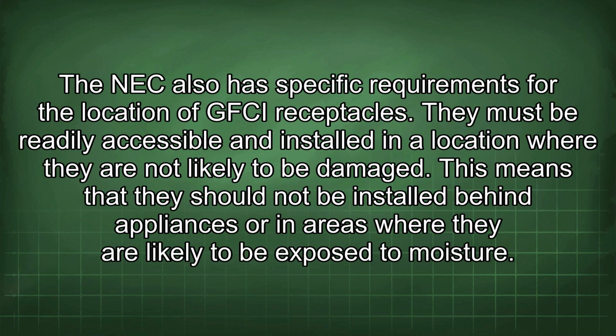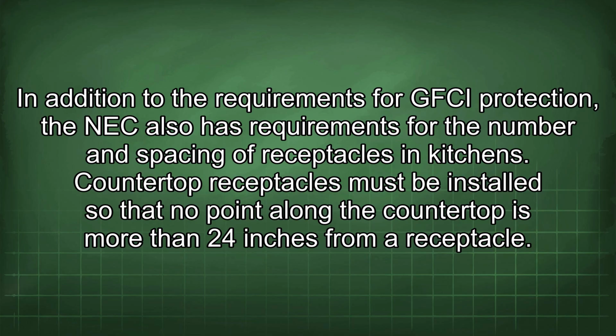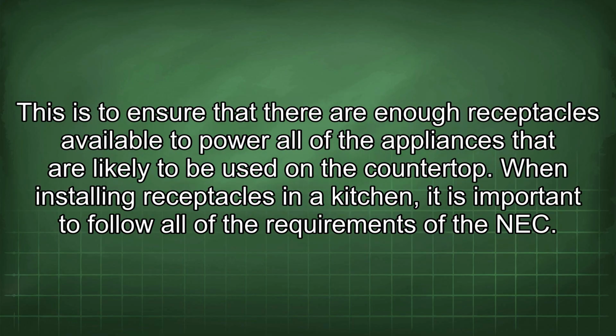The NEC also has specific requirements for the location of GFCI receptacles. They must be readily accessible and installed in a location where they are not likely to be damaged. This means that they should not be installed behind appliances or in areas where they are likely to be exposed to moisture. In addition to the requirements for GFCI protection, the NEC also has requirements for the number and spacing of receptacles in kitchens. Countertop receptacles must be installed so that no point along the countertop is more than 24 inches from a receptacle. This is to ensure that there are enough receptacles available to power all of the appliances that are likely to be used on the countertop.